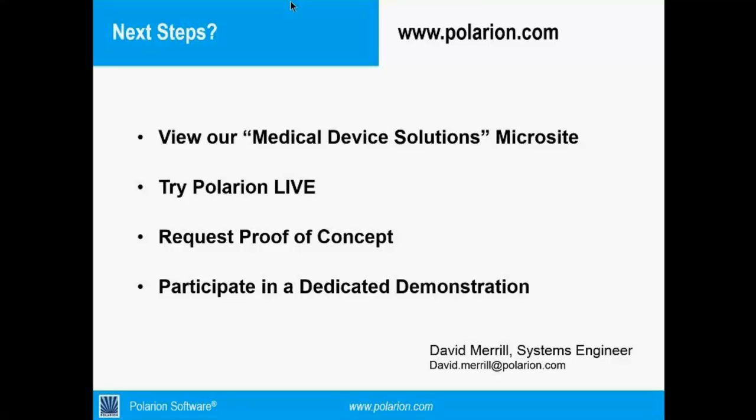Thank you. The only other thing that I could add from a Polarion perspective, it doesn't matter if you begin with harms or you begin with hazards and link them later on. If we think a little bit, maybe not so much about hazards only, but about the FMEA process, there's three major phases to that. There's the system FMEA, the design FMEA and the process FMEA. And the invitation, certainly in Polarion, is to begin this process as soon as possible with all the relevant information that you have.